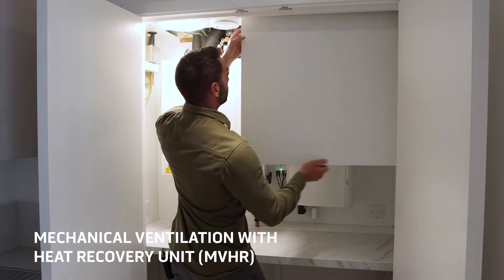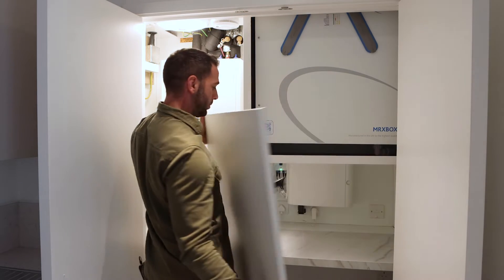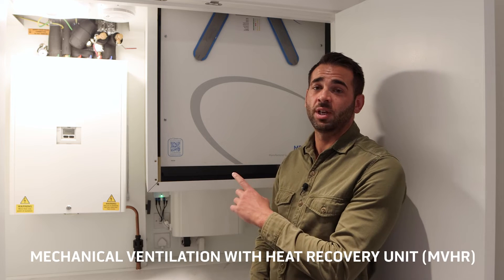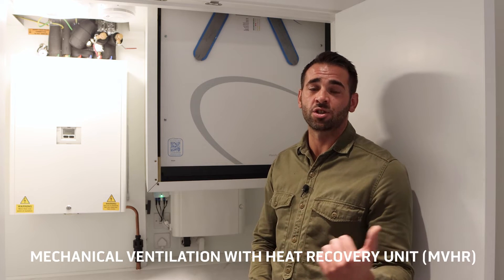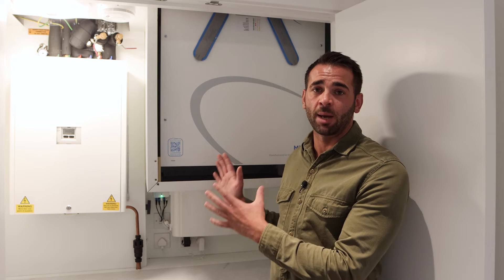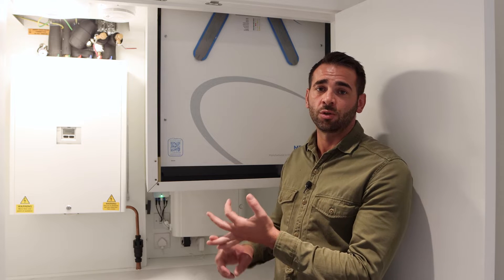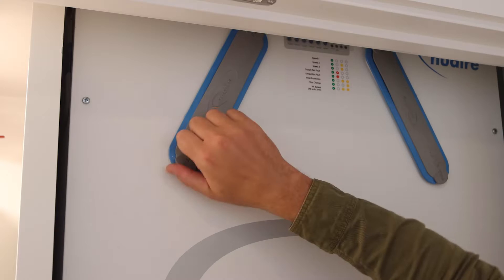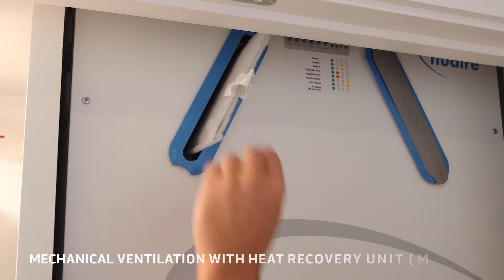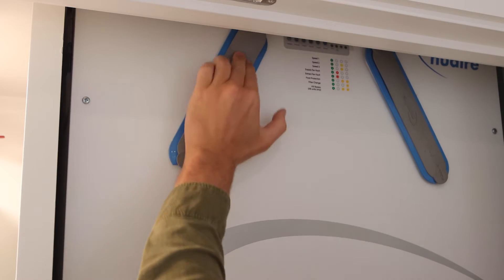I'm now going to show you how to take off the panel for the MVHR unit, which is the mechanical ventilation heat recovery system for the apartment. This is the MVHR unit — it controls the extract and the supply to the apartments. Don't ever turn the unit off; it needs to be kept on at all times to avoid any buildup of condensation or dust inside the apartment. These are the filters — they can be taken out to be cleaned once every three to four months with a hoover to clear any dust or debris inside the unit.